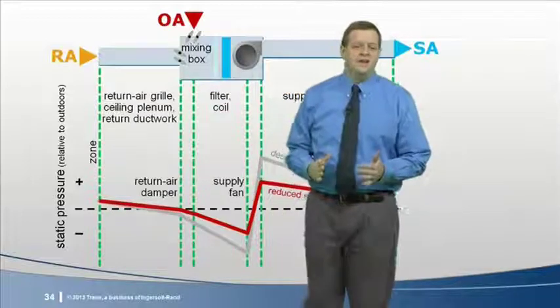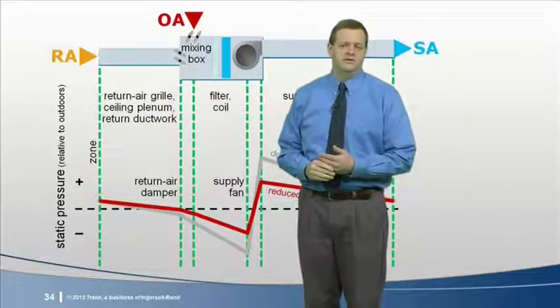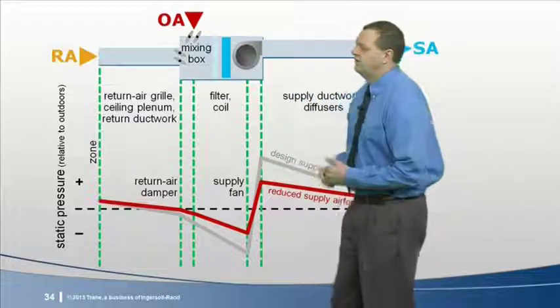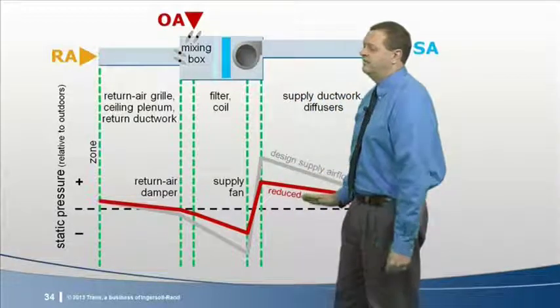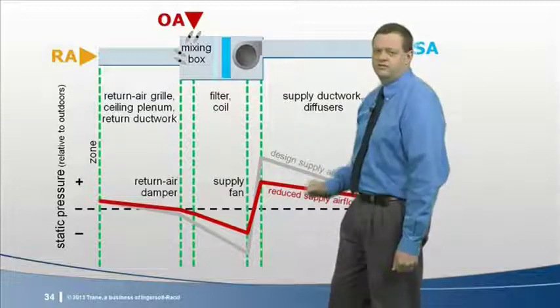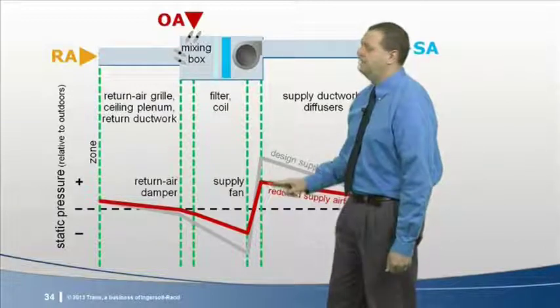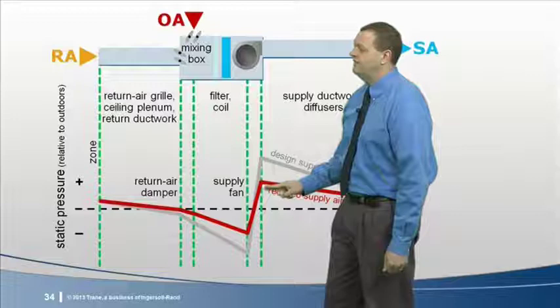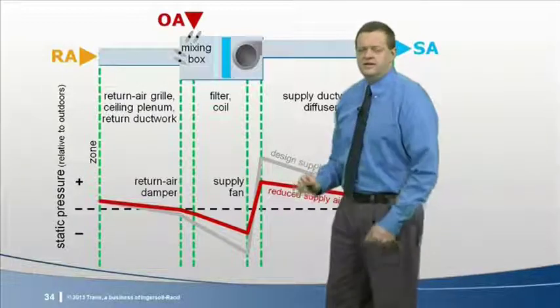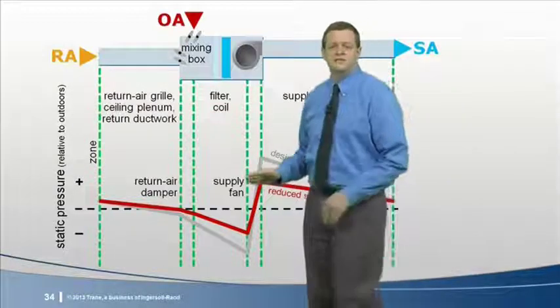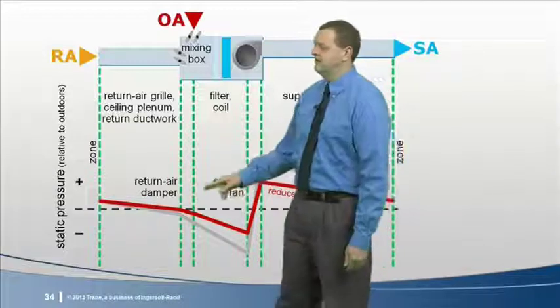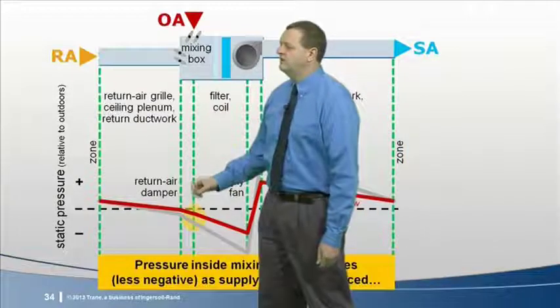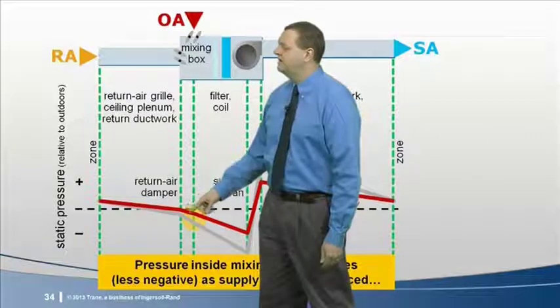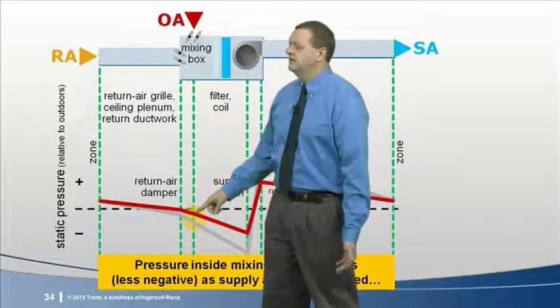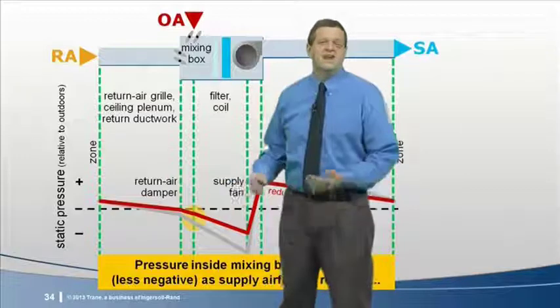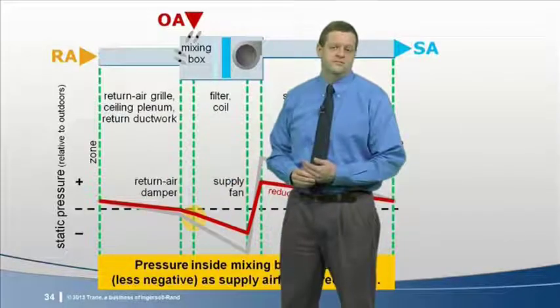Now let's see what happens as supply airflow decreases during part load operation. Pushing less air through the supply ductwork and diffusers results in less pressure loss. So the fan doesn't have to generate as high a pressure at the fan discharge. In this same manner, moving less air through the return air path also results in less pressure loss. This causes the static pressure inside the mixing box here to increase. That is, it's not as negative as it was at design airflow.